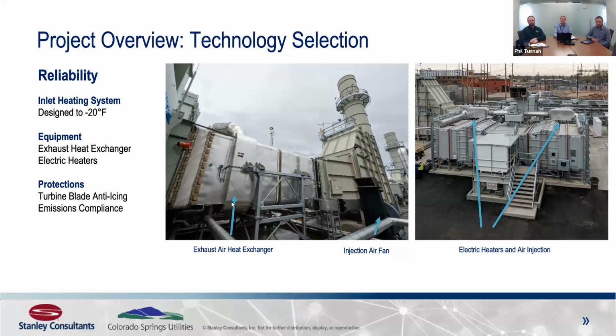As well, when temperatures get too cold, the air gets so dense that you get a very oxygen-rich combustion, which affects your NOx emissions. So we warm up the air just enough to make sure we're not exceeding what our permit allows. This system was an effective approach on this project, basically injecting warmed air into the inlet by stealing the exhaust heat, the waste heat coming out before it goes into the exhaust and out the stack.